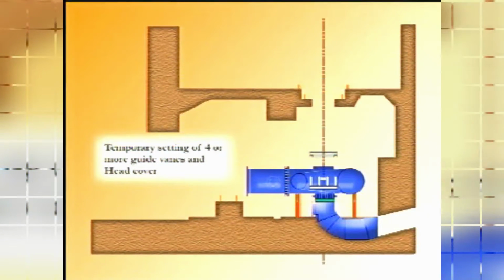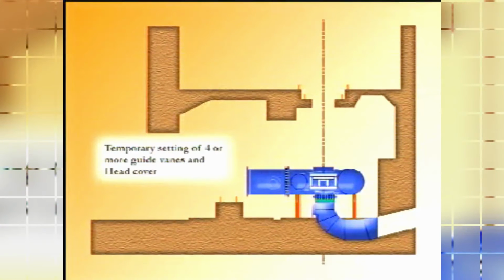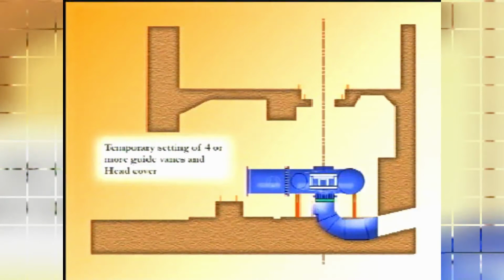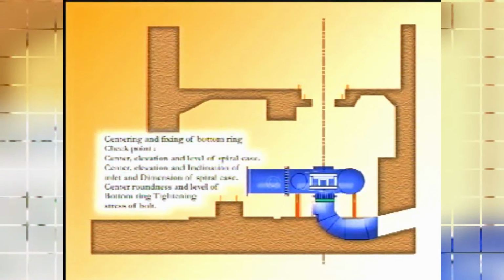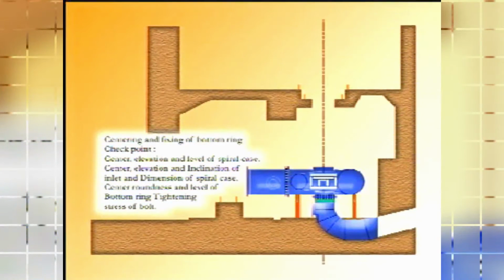Temporary setting of 4 or more guide vanes and head cover. Centering and fixing of bottom ring. Checkpoint, center, elevation and level of spiral case. Center, elevation and inclination of inlet and dimension of spiral case. Center roundness and level of bottom ring.